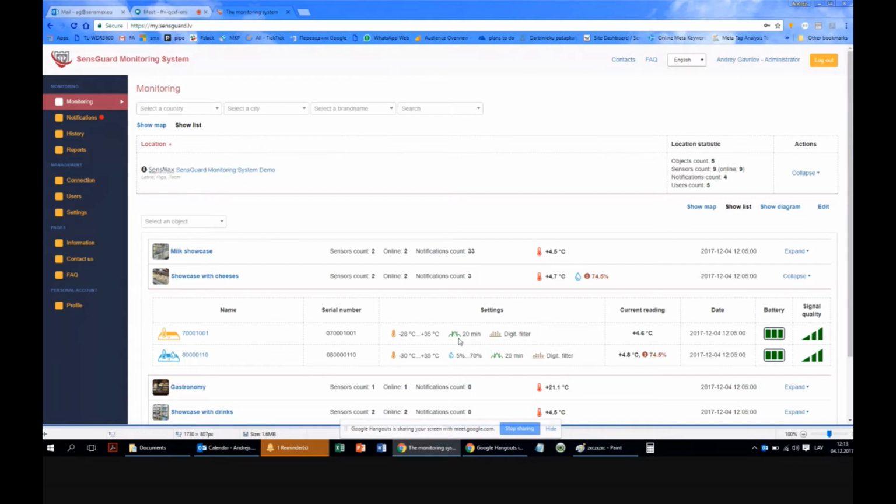This temperature doesn't change so fast, and therefore, if we open the refrigerator and take the product, then close it back, then temperature will rise for some seconds, as well as some equipment needs defrost, and they are doing it automatically sometimes per day. Therefore, we don't need notification if temperature goes up for example, for half an hour and returns back.